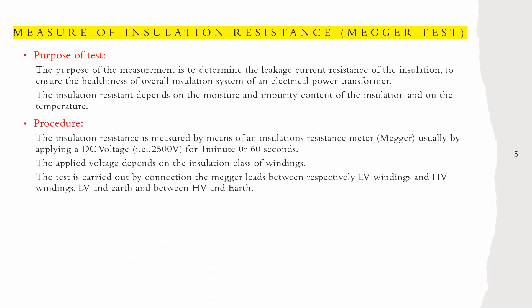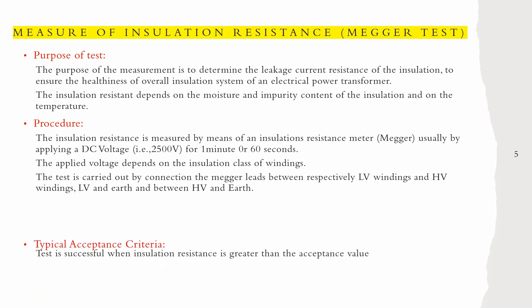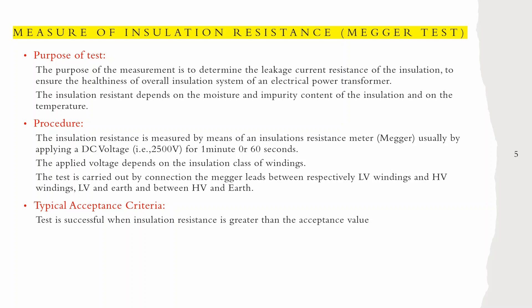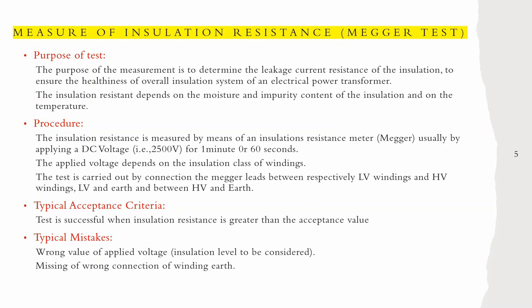The procedure: insulation resistance is measured by means of an insulation resistance tester (megger), by applying DC voltage — for example, 2500 volts (2.5 kV) — for one minute or 60 seconds. The applied voltage depends on the insulation class of the winding. The test is carried out by connecting the megger leads between LV winding and HV winding, LV and earth, and between HV and earth. Acceptance criteria: successful when insulation resistance is greater than the acceptance value. Typical mistakes: wrong applied voltage, missing or wrong connections of winding to earth.